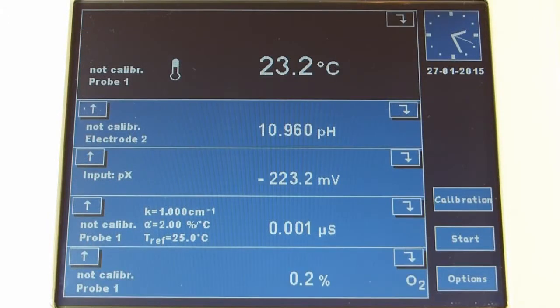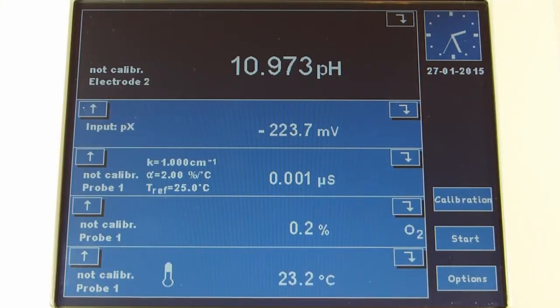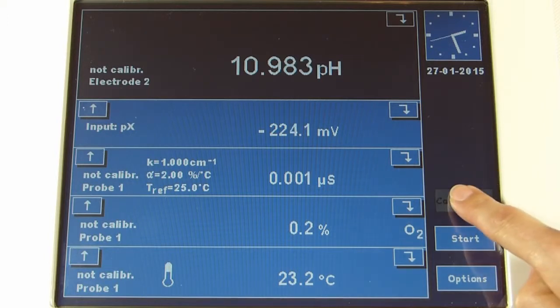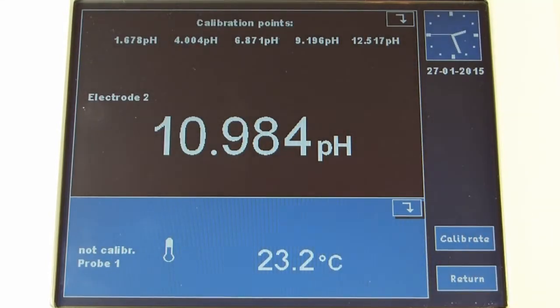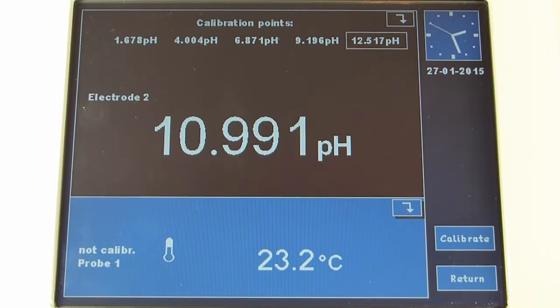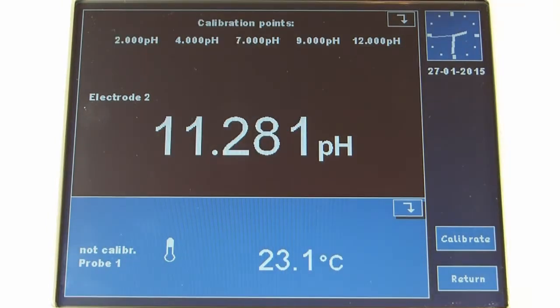When the electrode, cell or sensor needs to be calibrated, choose the calibration mode for the function placed at the top of the screen. For example, to calibrate the electrode in the pH function, move the function to the top of the screen. Measuring mode. Next, press and hold the calibration button until the calibration screen appears. Calibration mode. It contains all the parameters related to the calibration process. To change the calibration parameters, enter the parameters screen.